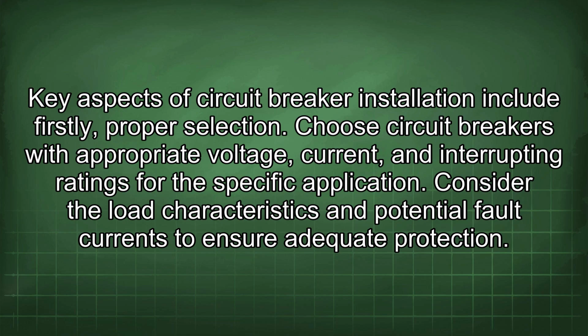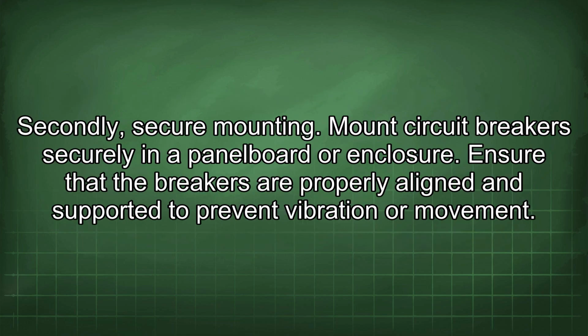Key aspects of circuit breaker installation include: firstly, proper selection. Choose circuit breakers with appropriate voltage, current, and interrupting ratings for the specific application. Consider the load characteristics and potential fault currents to ensure adequate protection. Secondly, secure mounting. Mount circuit breakers securely in a panel board or enclosure. Ensure that the breakers are properly aligned and supported to prevent vibration or movement.